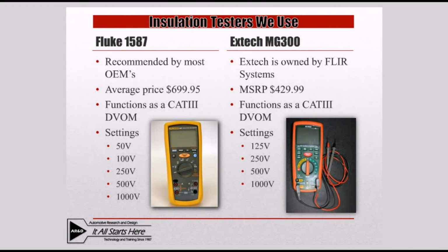The MG300 is made by Extech, a company you may be less familiar with. Extech is owned by FLIR Systems, better known for thermal imaging cameras. This unit has a lower price point of around $430, is still a fully functional Category 3 digital volt ohm meter, and still has an insulation test range from 125 volts up to 1000 volts, covering all vehicles currently in production. What it lacks, which is really just a convenience feature, is the remote actuation button on the test lead, so you have to apply the test button on the tester itself rather than from the end of the lead as with the Fluke.